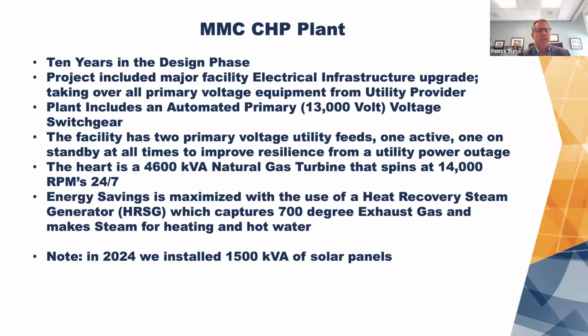The plant itself is a 4,600 kVA natural gas turbine. It generates approximately 70% of the electricity that we use each year, and it produces exhaust gas that's about 700 degrees. That exhaust gas is used to make steam for the facility for both heating, hot water, and sterilization in sterile processing. Also, as a note, we upgraded our utilities in 2024 by installing 1,500 kVA worth of solar panels. Next slide.